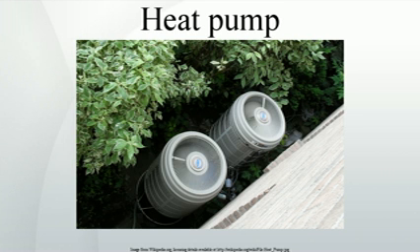One observation is that while current best practice heat pumps, ground source systems, operating between 0 °C and 35 °C, have a typical COP around 4, no better than 5, the maximum achievable is 8.8 because of fundamental Carnot cycle limits. This means that in the coming decades, the energy efficiency of top-end heat pumps could at least double. Cranking up efficiency requires the development of a better gas compressor, fitting HVAC machines with larger heat exchangers with slower gas flows, and solving internal lubrication problems resulting from slower gas flow.